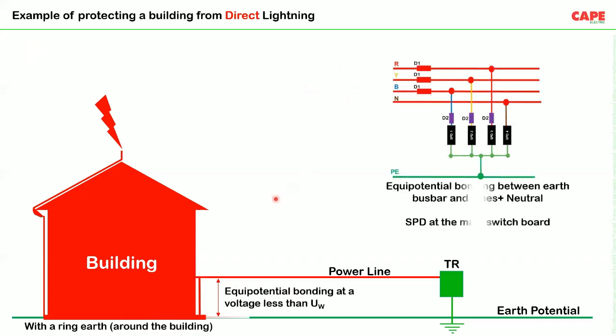Now, for example, I have used one type of connection. In the previous connection, I have shown 3 devices between line to neutral and 1 device between neutral and earth. In this case, I am connecting 3 devices between line to earth. The 4th device is between neutral and earth. So this kind of connection is called 4 plus 0. To understand it better, we can call them 3 plus 1 connection and 4 plus 0 connection. Both are a little bit different.